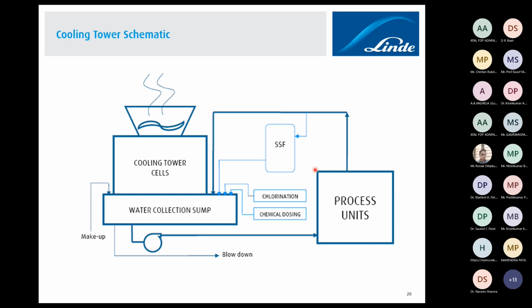And during this process some of the stream, I would say 2 to 2.5% of the water stream, we are just extracting out and putting into the side stream filter. We are using a small stream, that is why it is called side stream. We are not putting the entire stream in the filter, which is not required at all, because of how SSF works. It works on a principle.